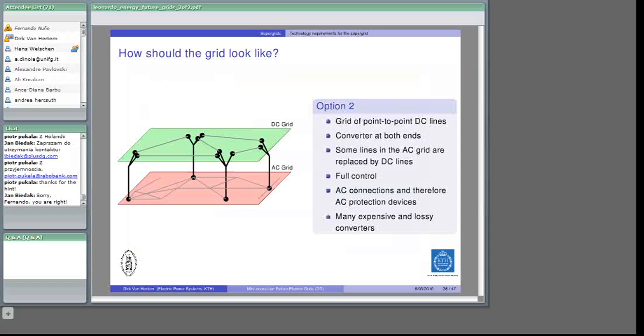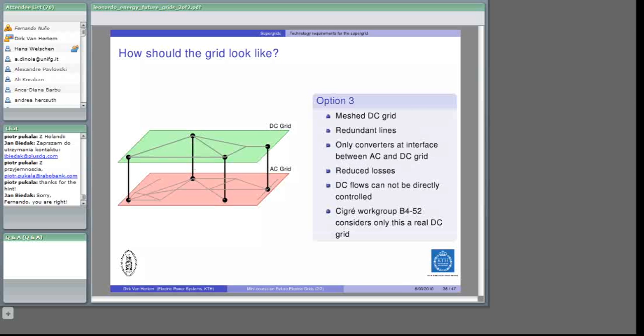The most advanced and most difficult situation is a meshed DC grid, where you have redundant lines, multiple connections, even DC connections without a node, and only converters placed at the interface between the AC and DC grid. This system would have lower losses than the previous one, and it has redundancy. The DC flow cannot be directly controlled, only the interface between AC and DC, where the flow can be controlled. For the CIGRE group B4.52 on DC grids, this is the only real DC grid that they consider.